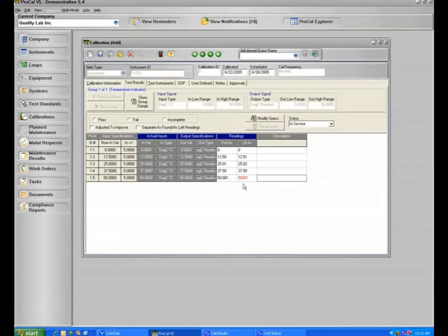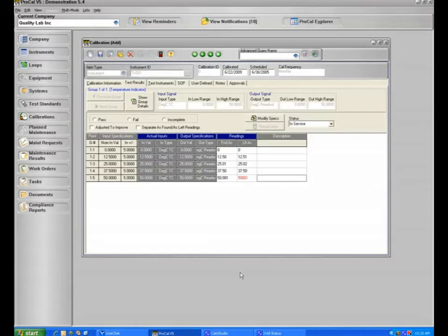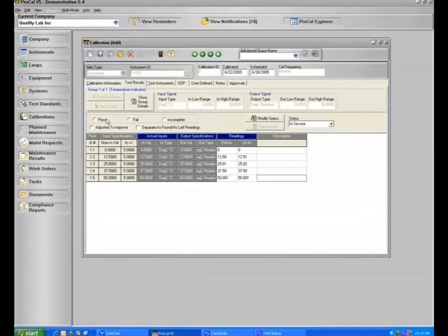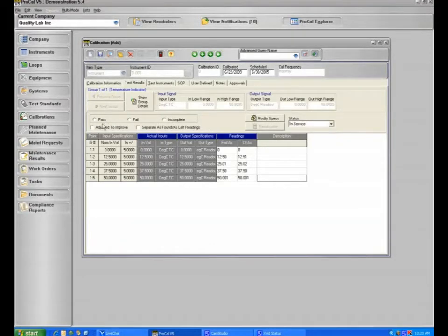This is a visual indication that the system has provided that that is an out of tolerance reading. Your technician can correct the work or he can go back and update it by including the decimal point if he forgot or any other type of mistake. A calibration can then be marked as passed, failed, or incomplete as well as adjusted to improve. And we'll say in this particular case it passed.